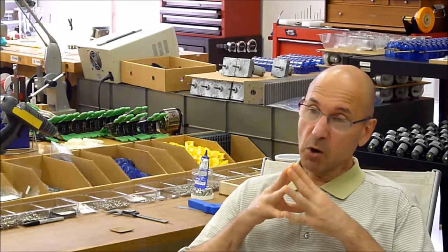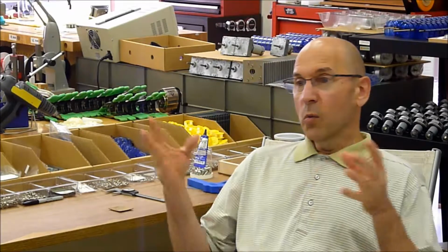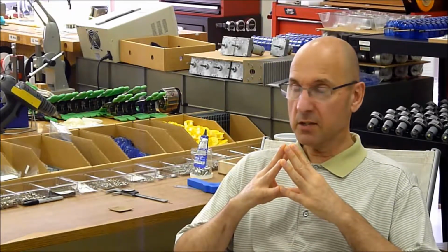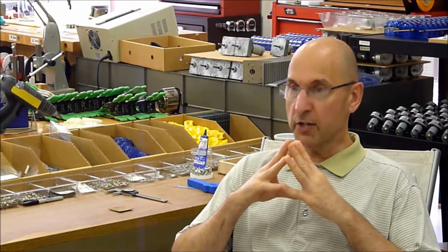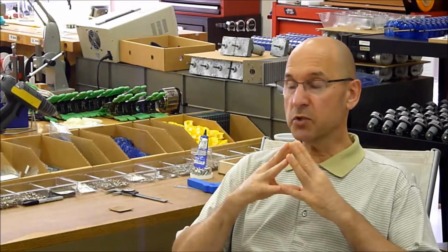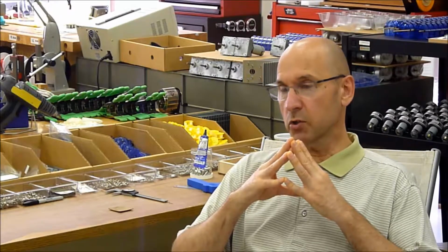These are fluorescent style. Remember, Ohm's Law applies to AC just like it does DC. So each light bulb was 40 watts. So it was a simple calculation. 4 times 40 was 160 watts per fixture, and then I multiplied that by the number of fixtures. So we knew the total wattage of the electrical lighting circuit that had failed. We also knew that the voltage was 120 volts. Remember, Ohm's Law applies to AC just like it does to DC. So it was a simple calculation of wattage divided by voltage, and that told us that there were too many lights on the circuit, because the amperage, after we used the equation, was higher than the wire size could handle, or the breaker size could handle. Remember, I said that they actually had the incorrect breaker in there, which was why it wasn't tripping.